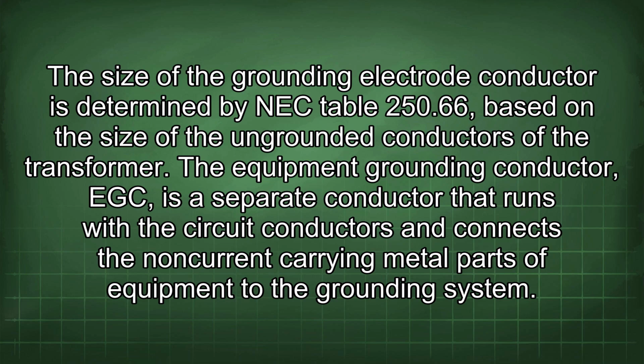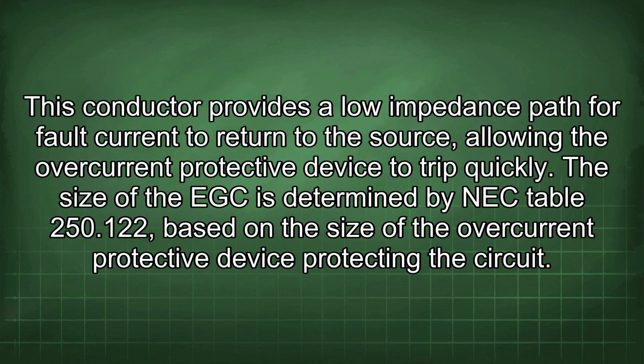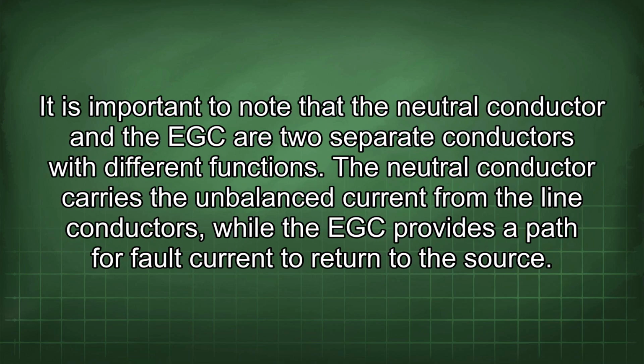The equipment grounding conductor, EGC, is a separate conductor that runs with the circuit conductors and connects the non-current carrying metal parts of equipment to the grounding system. This conductor provides a low impedance path for fault current to return to the source, allowing the overcurrent protective device to trip quickly. The size of the EGC is determined by NEC Table 250.122, based on the size of the overcurrent protective device protecting the circuit. It is important to note that the neutral conductor and the EGC are two separate conductors with different functions.